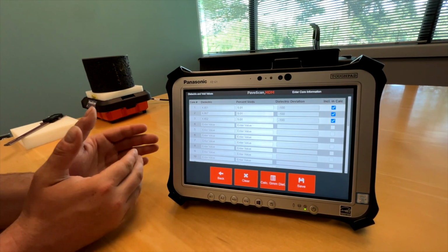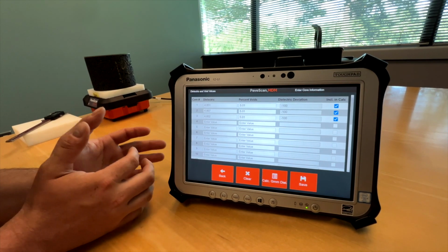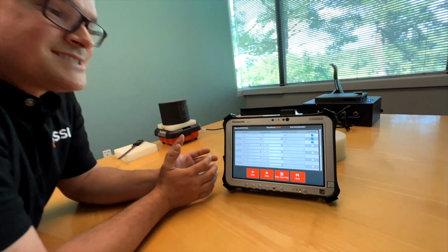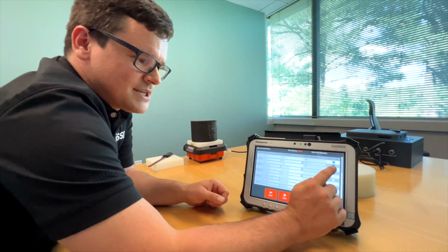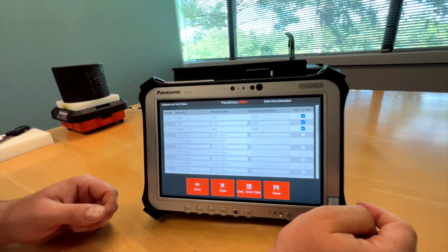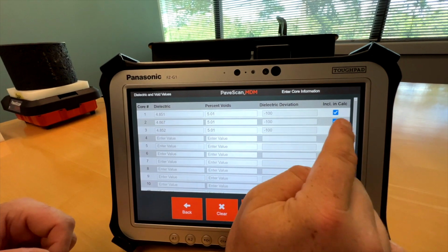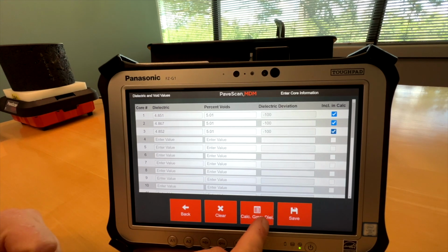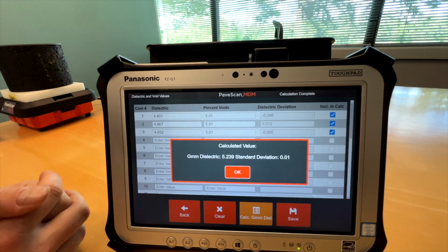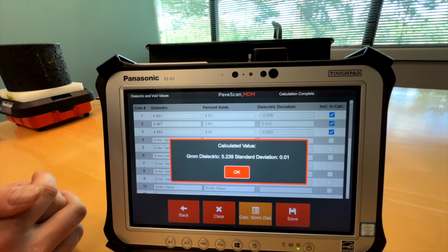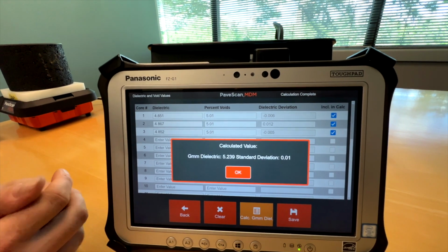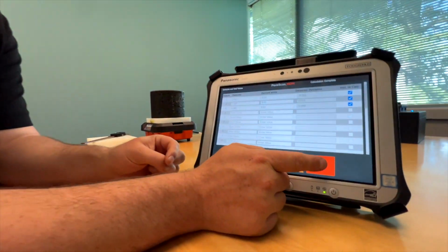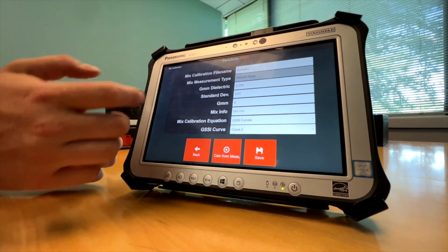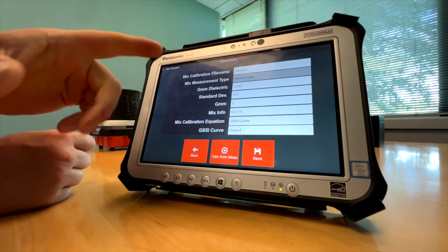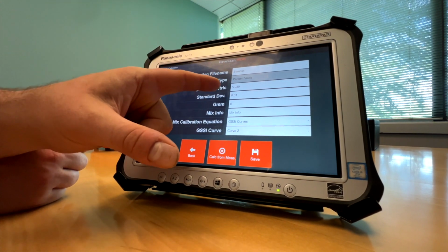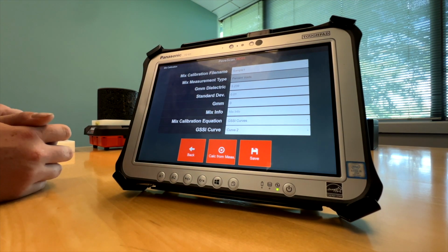I'd want to make sure that they were included in the calculations. If I got any really wonky, far out outlier readings from one of the samples or from just one of the measurements and I couldn't account for why, I might decide to not include that in the measurements. Instead, I'm going to include all 3 of these measurements. Okay. So I'm going to hit Calc GMM dielectric. GMM dielectric 5.239, standard deviation of 0.01. Perfect. Going to hit Save, which is going to advance me to this screen here, where now I have my mix calibration file name, my GMM dielectric listed as well as 5.239.